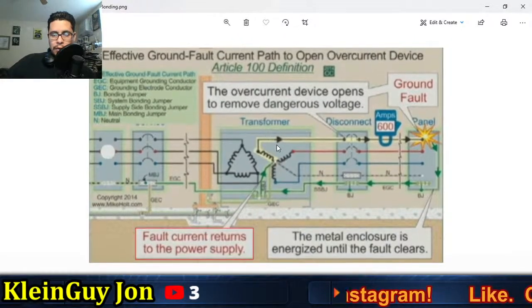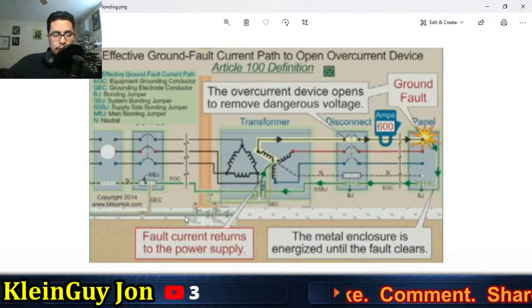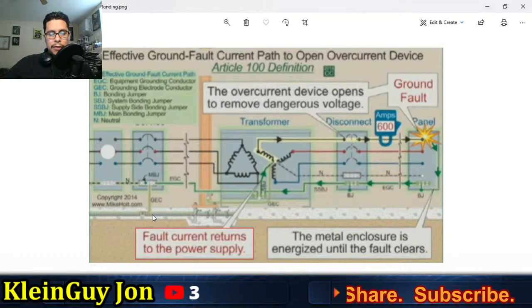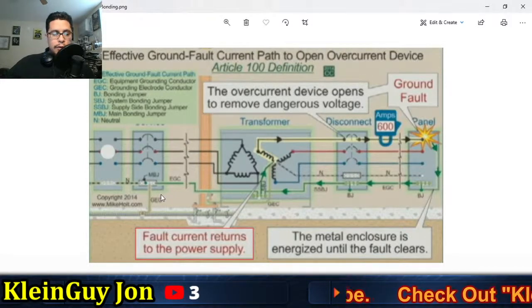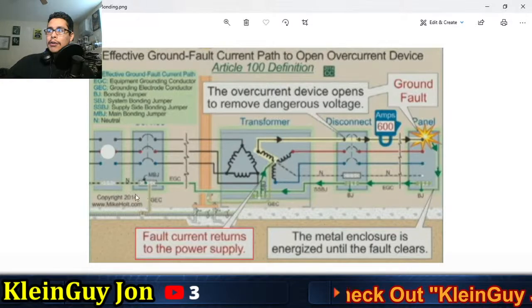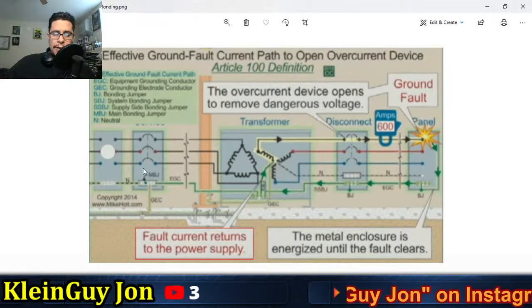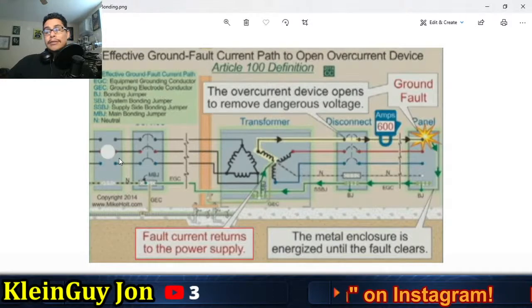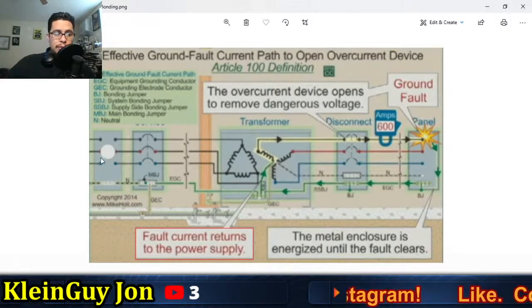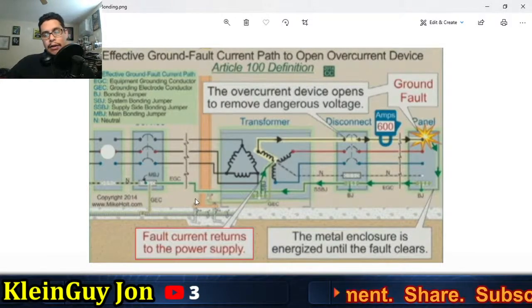480/277 volts, right? You have here now your ground rod or grounding electrode. Now, there's exceptions when it comes to grounding, right? You can use a rebar as a grounding electrode, or you can just drive a ground rod straight into the ground here. You could even do it at the meter can or after, at the disconnect, to run your ground. It depends on which state you live in. States are different with electrical code. Some states prefer that if you're gonna bond your ground to the neutral, you gotta do it at the meter. Or if you're gonna bond the ground, you're gonna do it at the service. Okay.